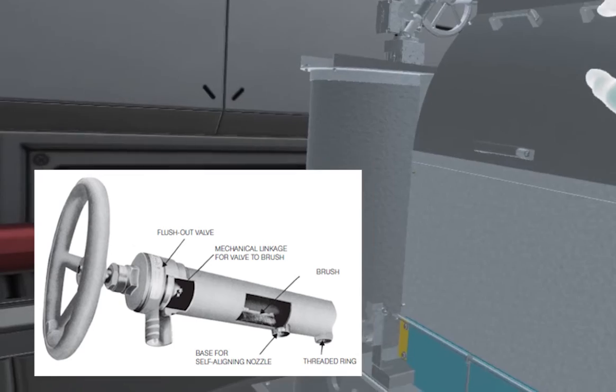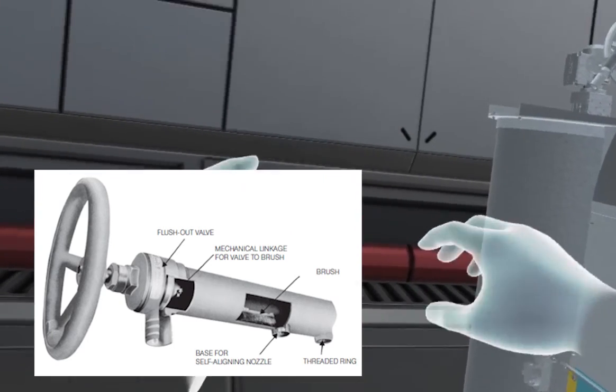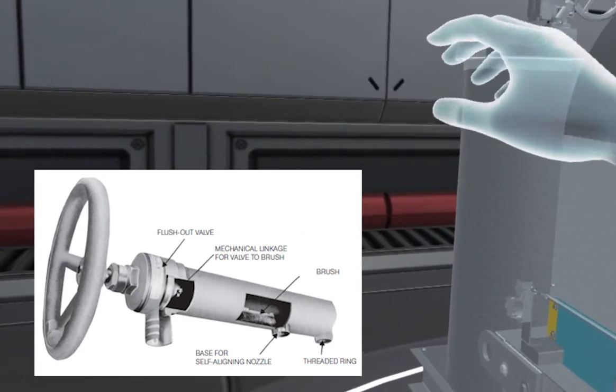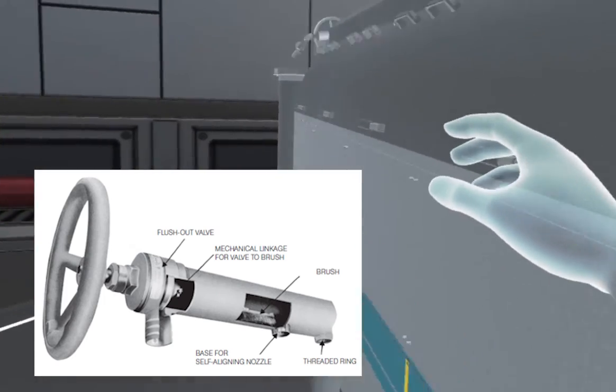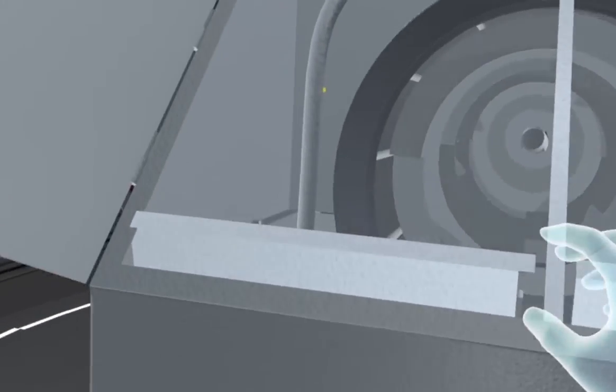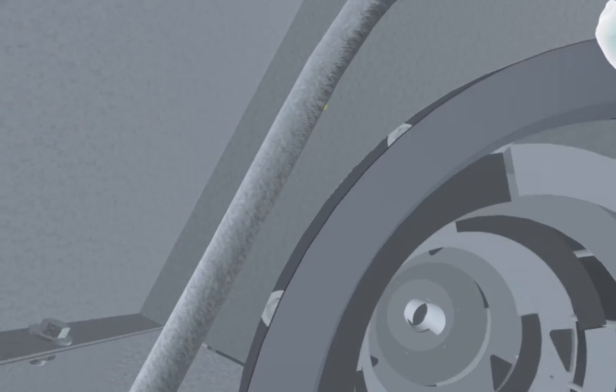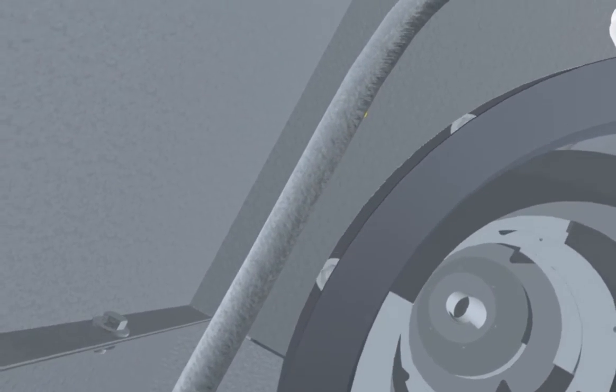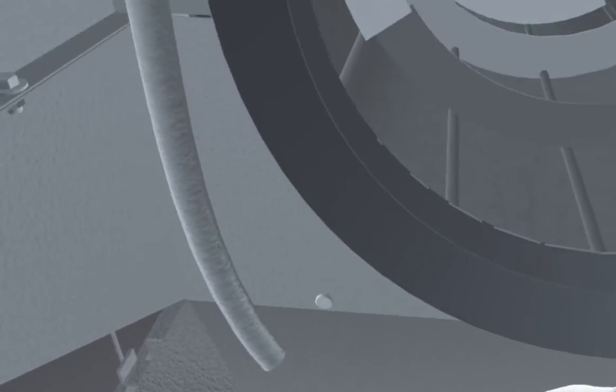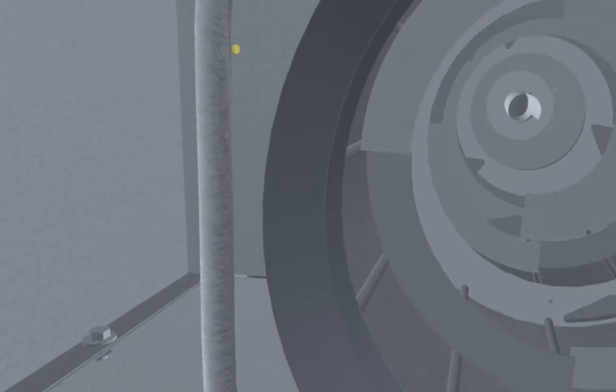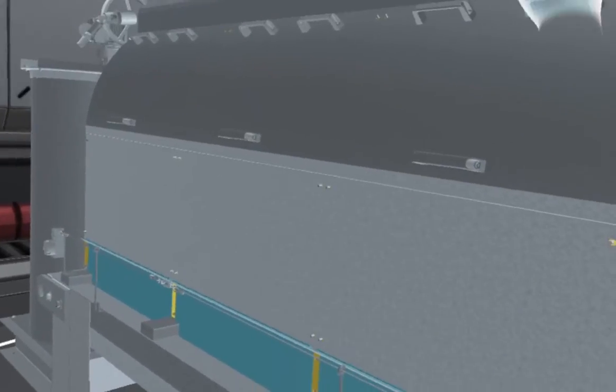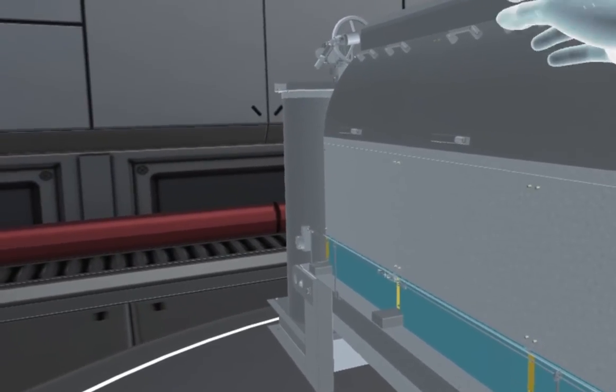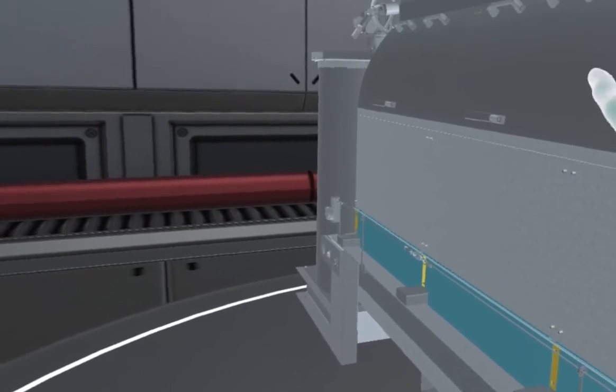So, what we have incorporated here is an internal brush, and you see this little paddle wheel at the end here. That is attached to a brush that goes the entire length of the spray header. And whenever you want to clean it, all you have to do is go over there and just turn that thing a couple times. The wire brush turns on the inside, cleans out the solids, and when that brush is turned, it actually opens a valve here at the end of the spray header that now lets all those solids that are cleaned off fall down into the discharge chute. And they go on with the thickened solids. And then when you crank it back the other way and close it again, it closes that valve, and then it does a little bit more fine cleaning.